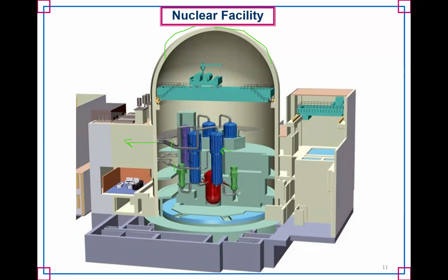But the concern would be if these pipes break for one reason or another, you now have very hot water, maybe 500 or 600 degrees, or even steam perhaps, that immediately is in an environment that, let's say this is 2250 psi. Now it's essentially in an ambient environment. And so what happens is that it expands very rapidly.